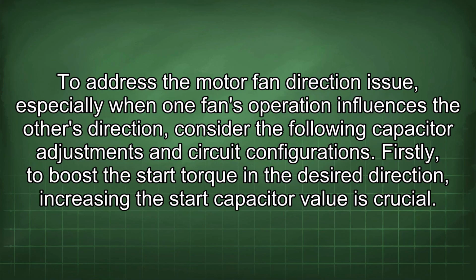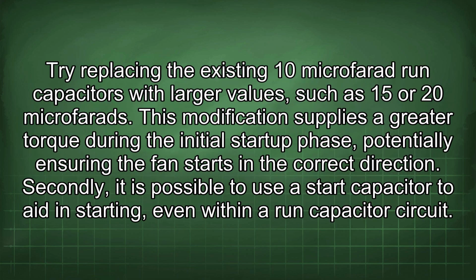To address the motor fan direction issue, especially when one fan's operation influences the other's direction, consider the following capacitor adjustments and circuit configurations. Firstly, to boost the start torque in the desired direction, increasing the start capacitor value is crucial. Try replacing the existing 10 microfarad run capacitors with larger values, such as 15 or 20 microfarads.